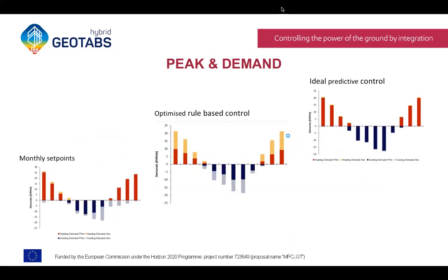Now, as you can see, the monthly set points here, as I played with it, are quite a big part on the secondary system. But as I put the set points in my simulation, you see that there's quite a big imbalance between the heating and cooling demand on the bore field. Because if you estimate the surface of the red bars and the blue bars, you see that the red bars take much more energy than the blue bars.